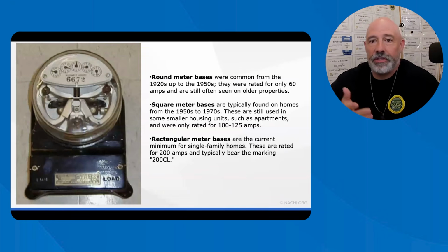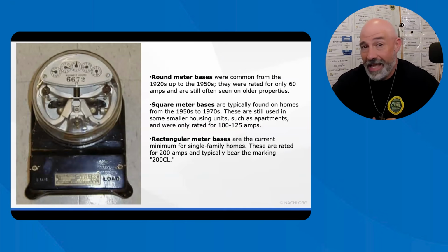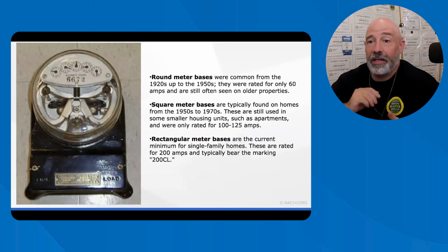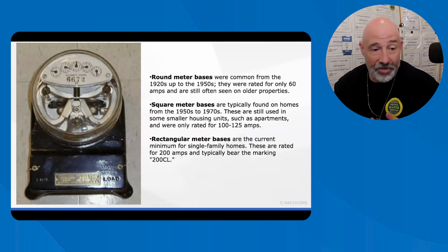As meters have increased in capacity over the years, the meter bases have changed. So you can actually see different meter bases from the earliest meters, such as this one here. Understanding the meter base is an important part of being able to properly evaluate the maximum available amperage of the home, believe it or not, but it should not be relied on completely when sizing the service.